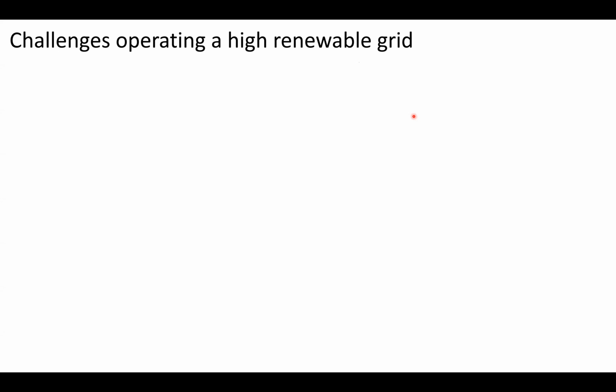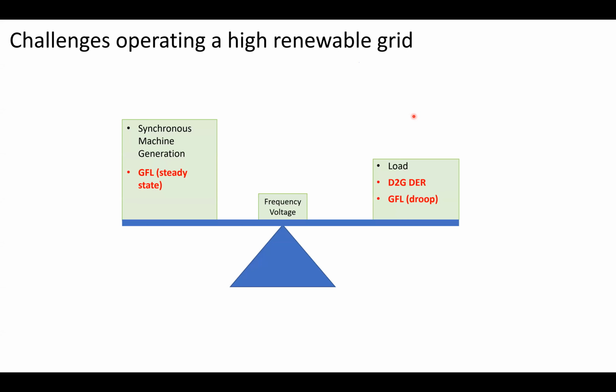So, challenges of operating a high renewable grid. As a lot of you folks do know, it's a seesaw. And conventionally for everyone, you're always trying to balance frequency and voltage with your synchronous machine generation and your load. However, for us, it's been a little bit different over the past few years. It's been a balance of our grid following inverters that have been set point dispatched in a steady state time frame, added on to our synchronous machine generation. And then on the other side of the seesaw, we have our direct to grid DER, which is subtracting from the load that we're trying to balance. So it's a negative load in a sense for steady state.